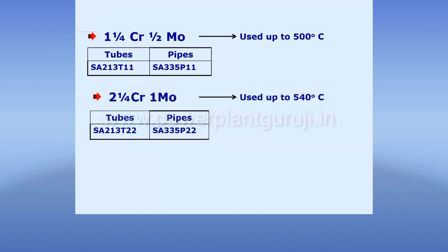Where the component temperature is not expected to increase beyond 540 degrees centigrade, we can generally use T22 metallurgy. But nowadays in the final superheater and final reheater, the steam temperature itself is around 540 degrees, so the metal temperature is in the range of around 555–560 degrees centigrade. There, T22 metallurgy cannot be used again, so where the metal temperature is expected to go beyond 540 degrees centigrade, we use an even higher metallurgy.